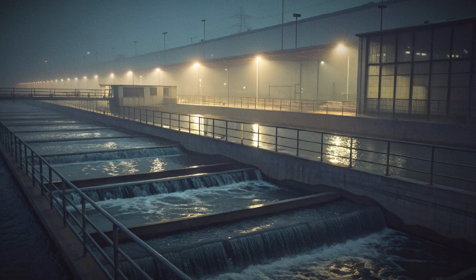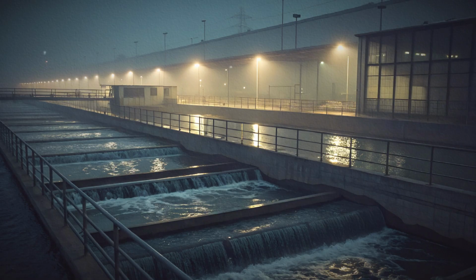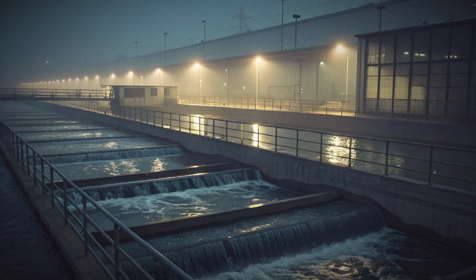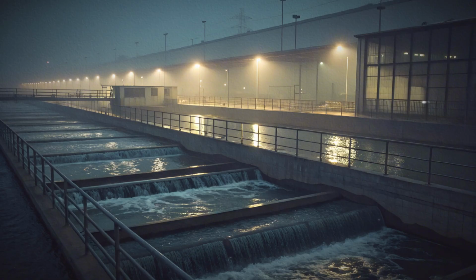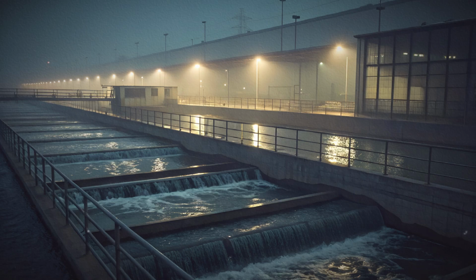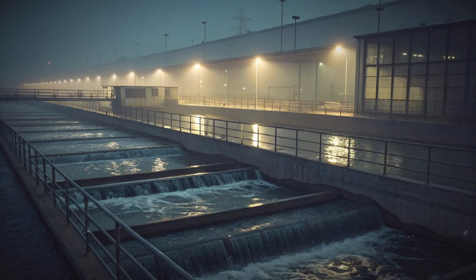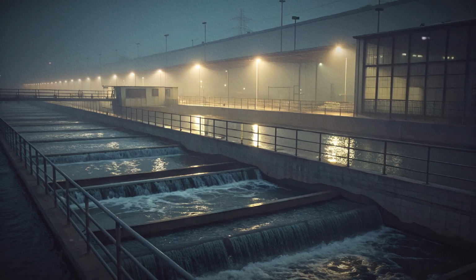Screens and racks are the first physical barriers within an intake. Coarse screens intercept branches, leaves, and larger floating objects. These screens are sometimes equipped with mechanical rakes that remove the accumulated debris. Finer screens follow to capture smaller solids. Screen openings vary, but the principle is consistent: reduce solid load before water reaches treatment basins. Screen cleaning can be automatic or manual. Regular cleaning maintains throughput and prevents excessive head loss across the screen.